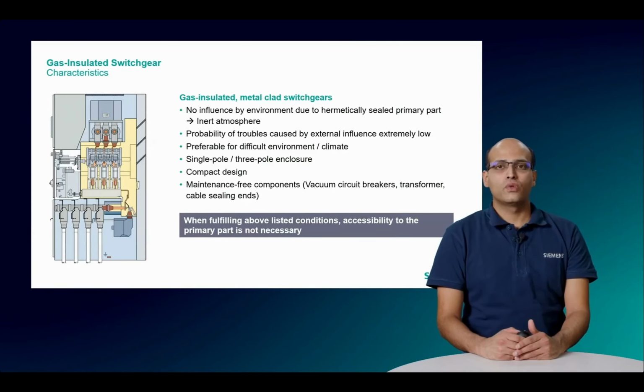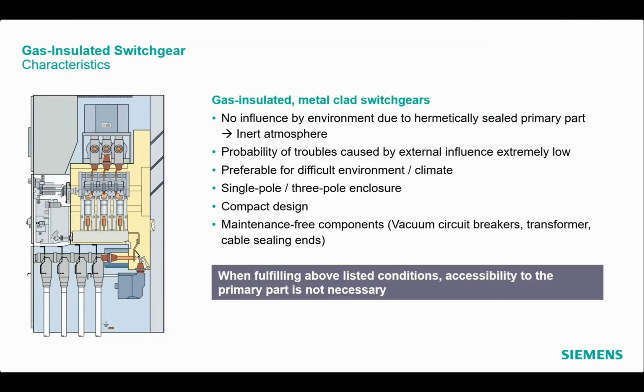Characteristics of gas-insulated switchgears. The gas-insulated metal-clad switchgears GIS use gas as the primary insulation medium. The insulating gas SF6 traditionally used has excellent dielectric properties but has impact on the environment because of it being a potent greenhouse gas. Because of this reason, Siemens is now moving to the next generation of environment-friendly gas-insulated switchgears which use the fluorine gas-free clean air technology. Let us now look into other characteristics of GIS.